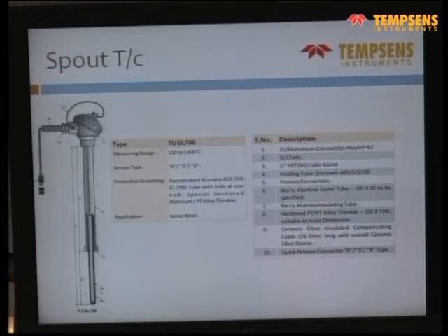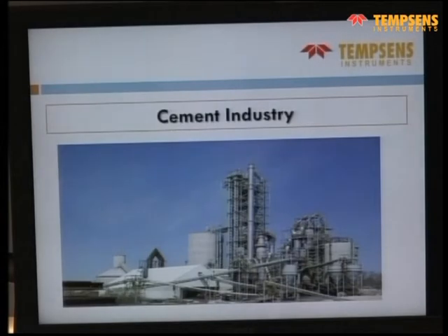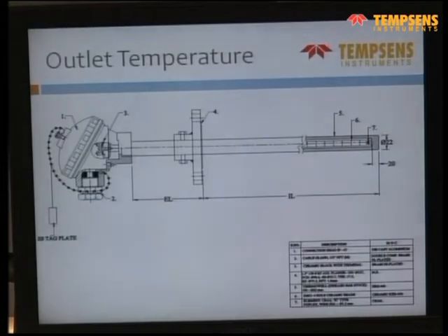This is at the end of the glass, it's called the spout thermocouple. In case of cement industry, this is at the kiln outlet temperature. This is normally made of HRS 446. It's a high temperature withstanding material, and inside can be an MI cable of SS310 and K-type element. And life here you can expect about 1 month or so, 1 month or 1.5 months is the life for such a thermowell. And in this case, the life would depend on how long your thermowell can withstand such an aggressive and high temperature application.